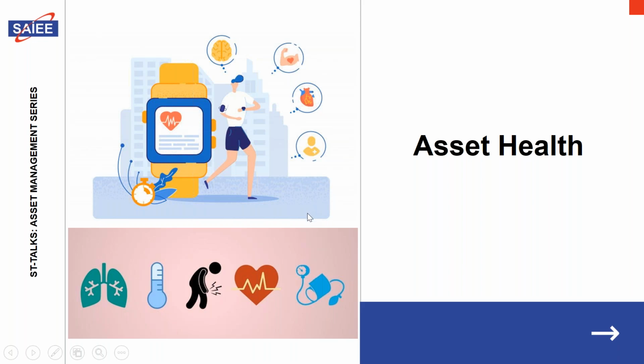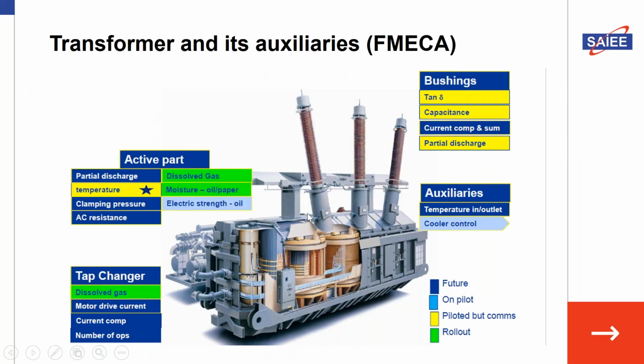So assets are very similar. I've taken an example here of transformers, and this graphic shows all sorts of sensing and measuring done at different parts of the transformer to try and get these proxy indicators of the status of health. On the active part there, inside the oil, of course, we check for dissolved gases. These gases are proxy indicators that your transformer may be susceptible to faulting and explosion.